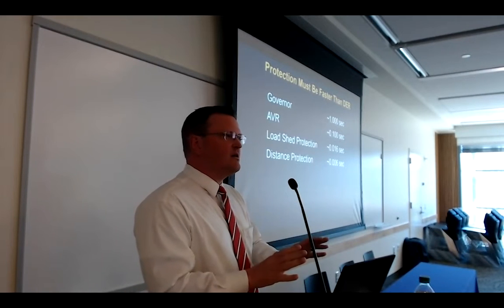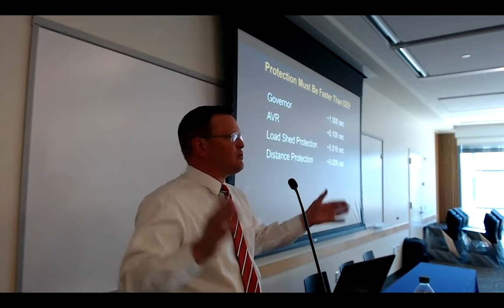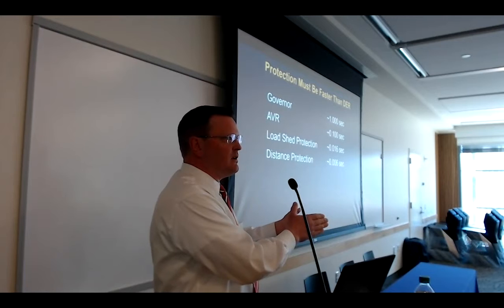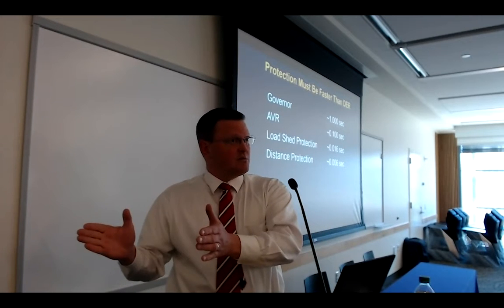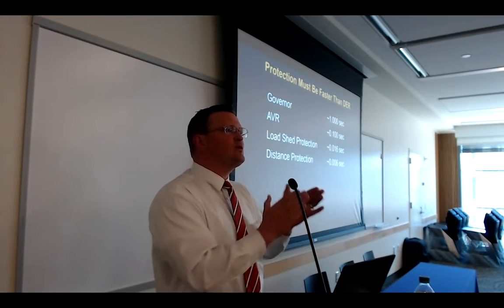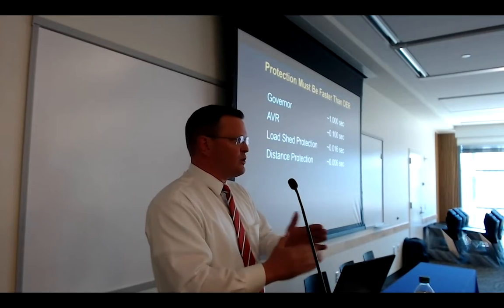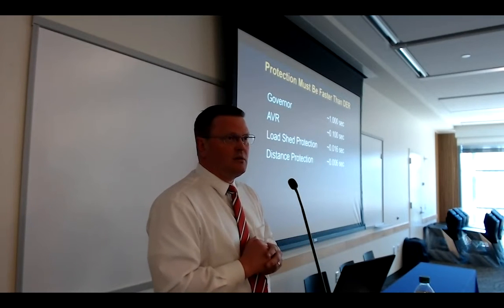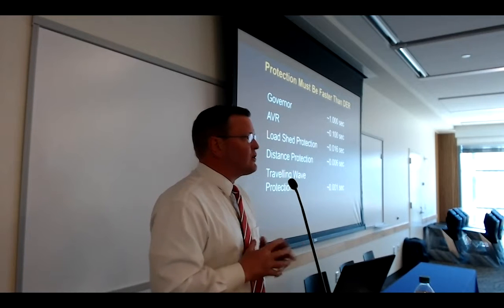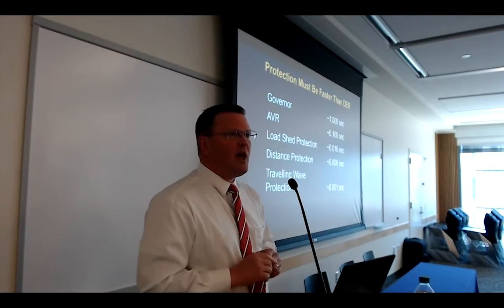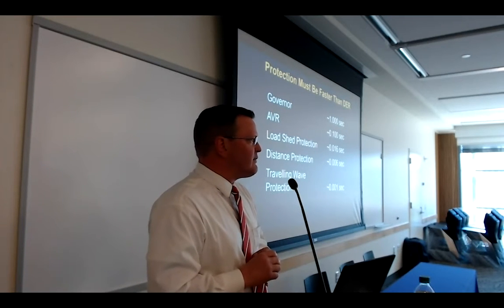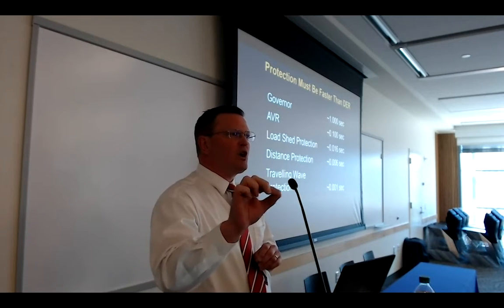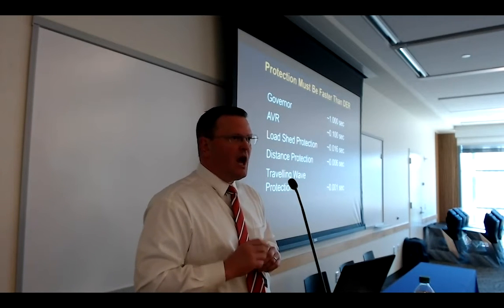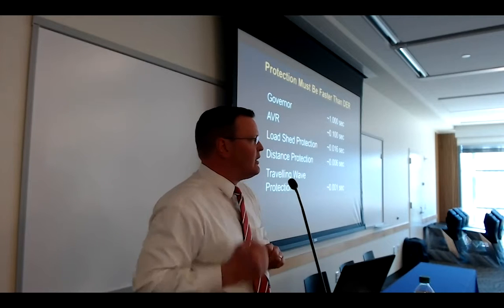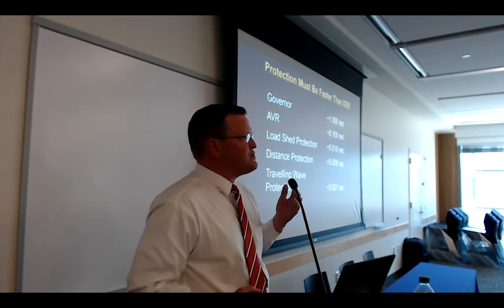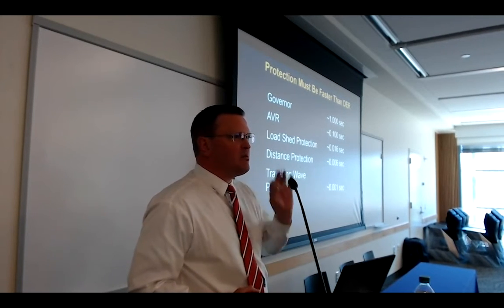This is designed—we all know Nyquist. Well, Nyquist works for comm systems, it works for control systems, and it also works for protection systems. There's an order of magnitude here for a reason. When you talk traveling wave protection, we've gone even better—now we're down to the millisecond. Traveling wave protection acts before the current even moves; we look for that reflected phenomena, that pulse of energy coming back from a change in impedance.